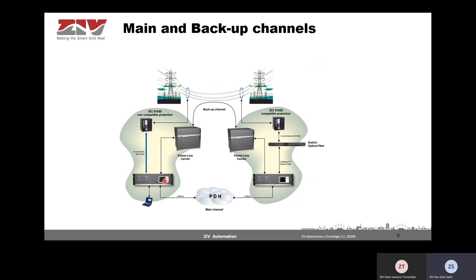Another example of redundancy: here we have, as a main channel, a digital one, and as a backup channel, an analog one which is sending commands through a power line carrier. This configuration is very common for strategic lines or very high voltage lines, because the reliability of power line carrier systems under specific conditions is very well known.